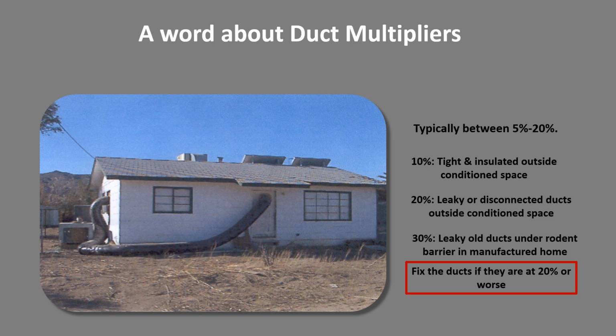and it's coming through the front door and back in through a window. And we can say, well, that's a dumb thing to do, but quite honestly, in the summertime, this house would have a lower duct multiplier than if it was in the attic. And like most people on this call today probably know, attics get really hot in the summertime.